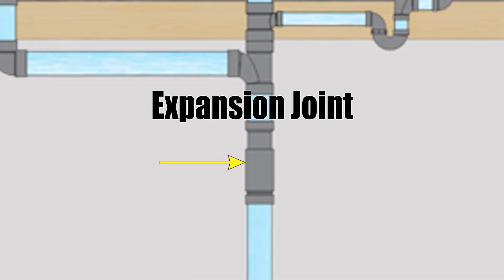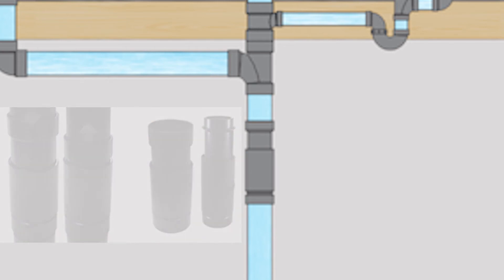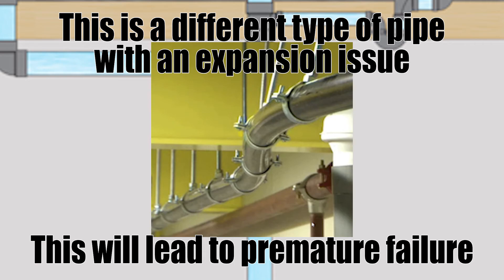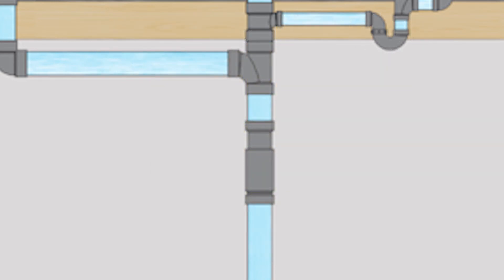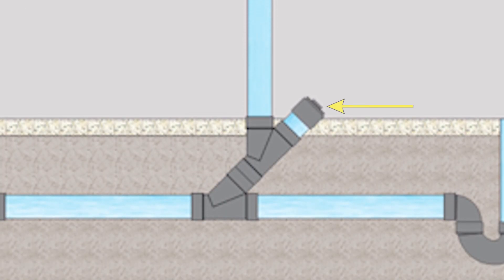In the middle of the soil or waste stack there's a device called an expansion joint. This is a telescopic joint that moves back and forth, makes a watertight seal, and allows for the building to settle. We don't want rigid pipe there because the building settling down on that soil or waste stack could cause it to bow or fracture from all the forces put on it. Putting in an expansion joint is a code requirement.